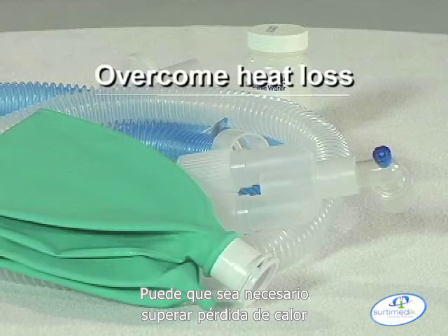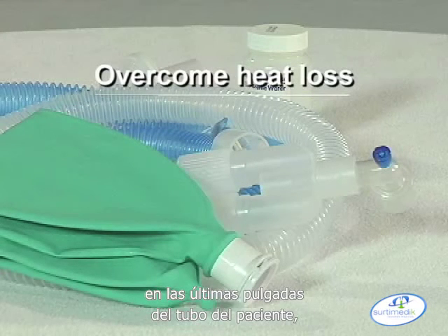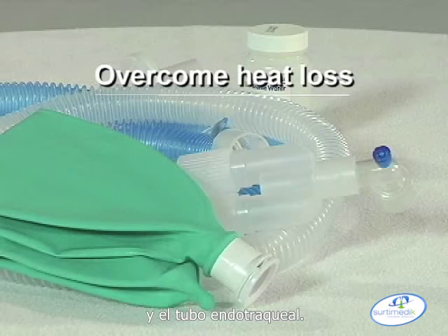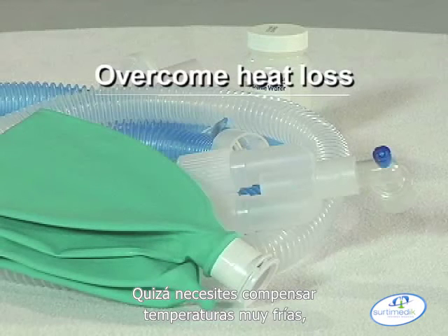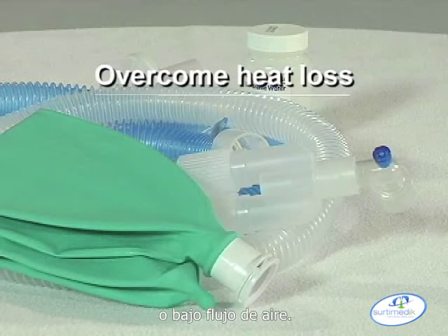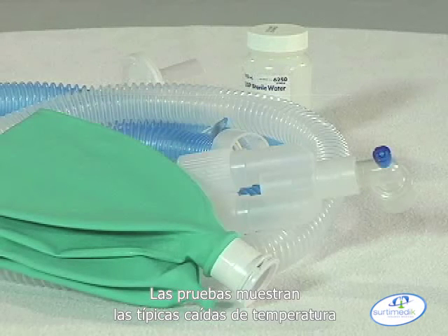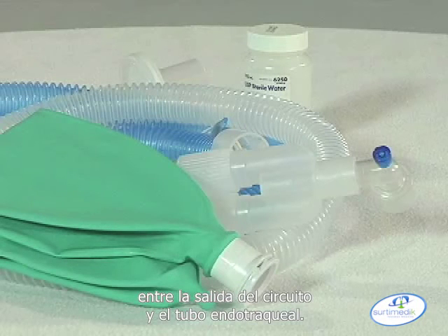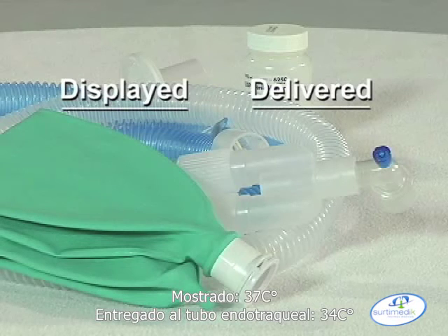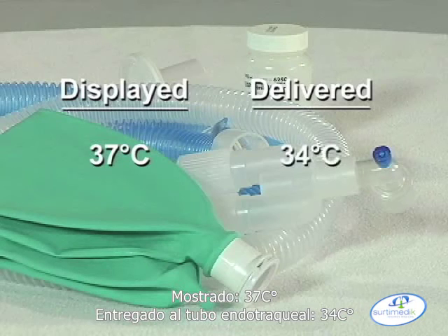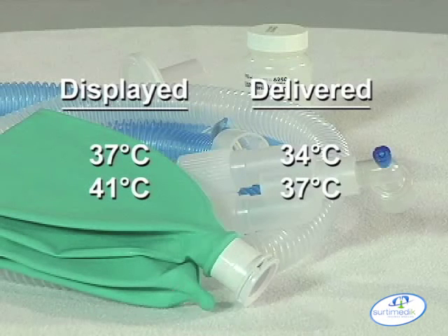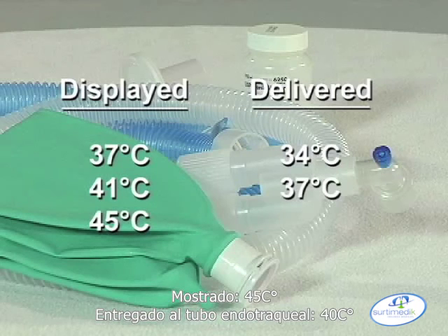It may be necessary to overcome heat loss in the last few inches of the tubing, cuff, patient Y, elbow, and/or ET tube. You may also need to compensate for very cold room temperatures and/or low airflows. Testing shows the following typical temperature drops between wick circuit output and ET tube. Displayed 37 degrees centigrade. Delivered at ET tube 34 degrees centigrade. Displayed 41 degrees centigrade. Delivered at ET tube 37 degrees centigrade. Displayed 45 degrees centigrade. Delivered at ET tube 40 degrees centigrade.